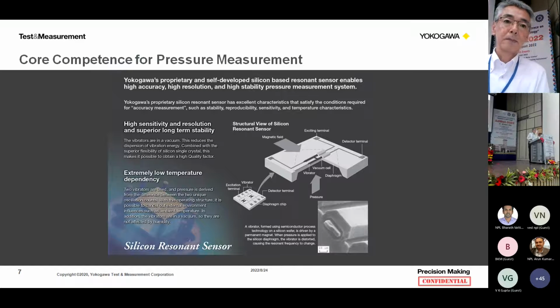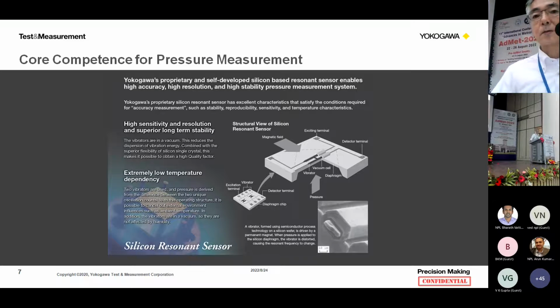So now we talk about some detail of silicon resonance sensors. The silicon resonance sensor is Yokogawa proprietary, self-developed and self-designed. This sensor is made of silicon single crystal using semiconductor process technology. There are two vibrators inside, and the pressure value can be obtained from the difference between two unique oscillation frequencies. So this sensor has excellent characteristics required for accurate measurement, such as stability, reproducibility, sensitivity, and temperature characteristics.